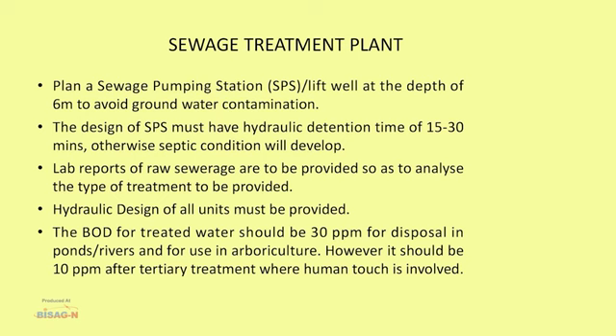Now comes the sewage treatment plant. Plan a sewage pumping station, that is SPS, or lift well at a depth of 6 meters to avoid groundwater contamination. The design of the SPS must have a hydraulic detention time of 15 to 30 minutes, otherwise septic conditions will develop. Lab reports of raw sewage are to be provided so as to analyze the type of treatment to be provided. Hydraulic design of all units must be provided.